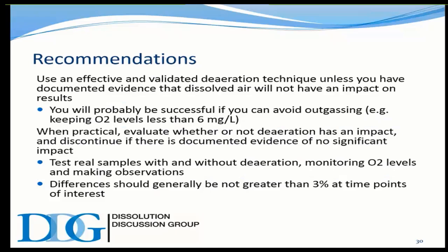The USP procedure, again, being a standard, I showed you a method in a slide back there that allowed one vessel to be heated to 41, and then you're pulling the media through a filter by applying a vacuum on a second jar. This is very effective, and dissolved gases really should not have an impact on results if it's been properly deaerated.